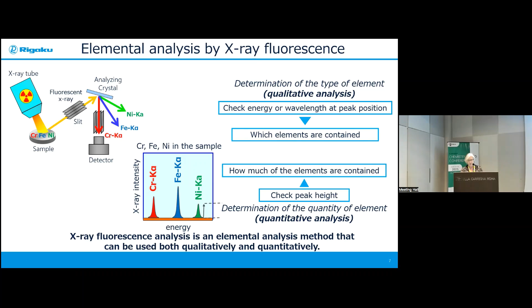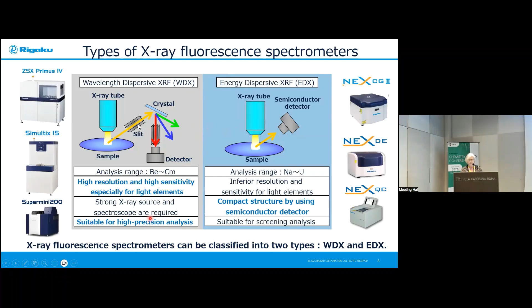Here we can see the difference between the hardware configuration of a WDXRF and an energy dispersive XRF. We have a different setup, and the elemental range is completely different to energy dispersive. Here we have smaller instruments, more benchtop, more used for screening, compact design, but as I said, more for screening analysis, not very accurate and not very precise. But if we look at our WDXRF, we have larger instruments, a better hardware design, bigger analytical range, and therefore a higher resolution and a higher sensitivity, especially for light elements. So this is really suitable for extremely accurate and extremely high precision analysis.